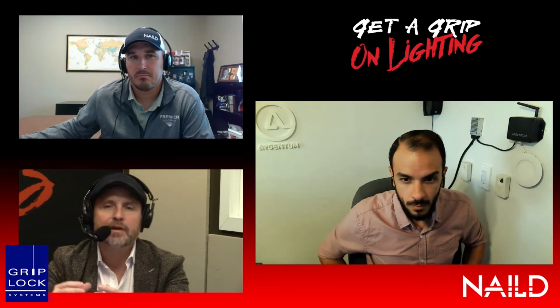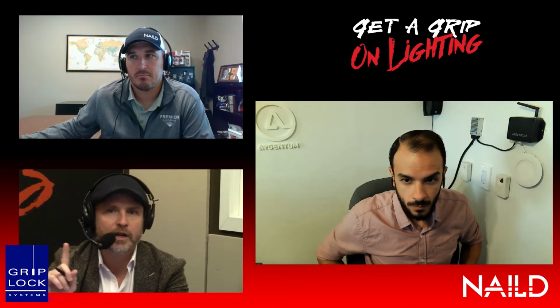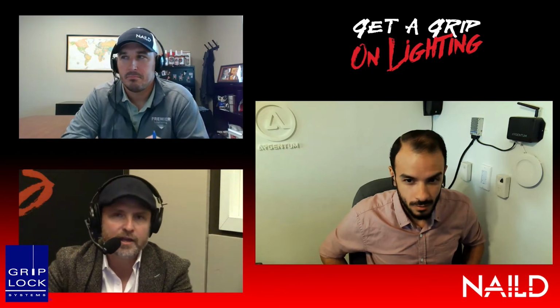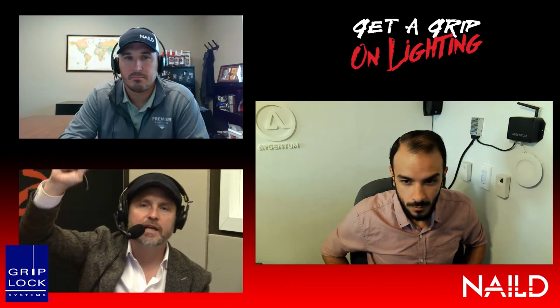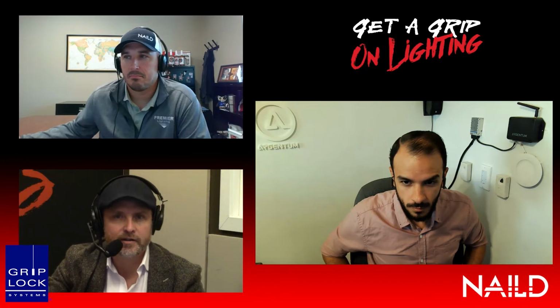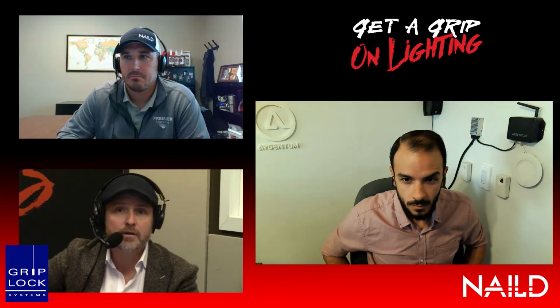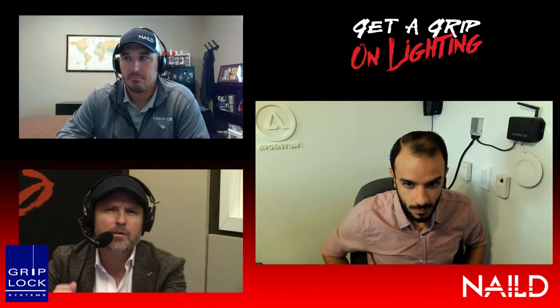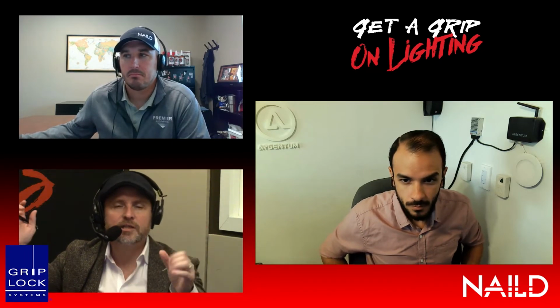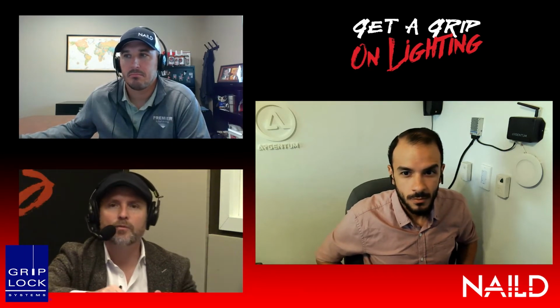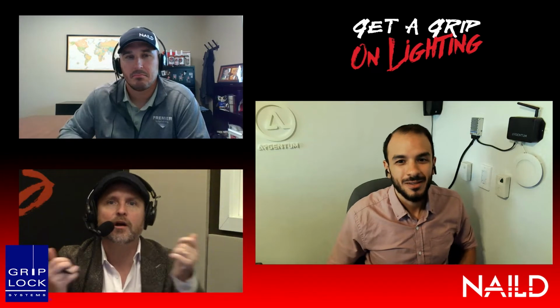You should still be mechanically protecting those cables. I don't care what anyone says. The number one thing is not that someone goes in the ceiling and gets blown out of the ceiling and starts on fire and dies. Yeah, that happens from time to time. God love those people, you know what I mean? But mostly it's because somebody's messing around, the plumber's up there and he smashes the BX cable, even the armored cable, and it causes a short.